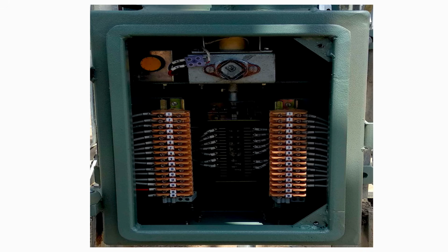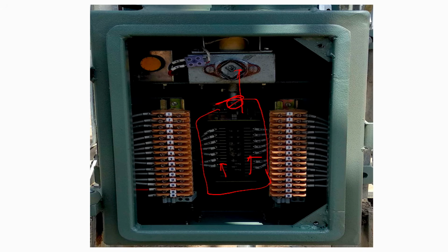If you would like to design a perfect interlock with isolator, first you have to concentrate on this part. This is the auxiliary switch. If your auxiliary switch is not able to perform, if it is not aligned with your isolator, you are not able to get a perfect interlock, because your contacts will not change over as per our requirement. So first, what you have to do is align the auxiliary switch with your isolator mechanism, so it moves as per the isolator blades' movement.